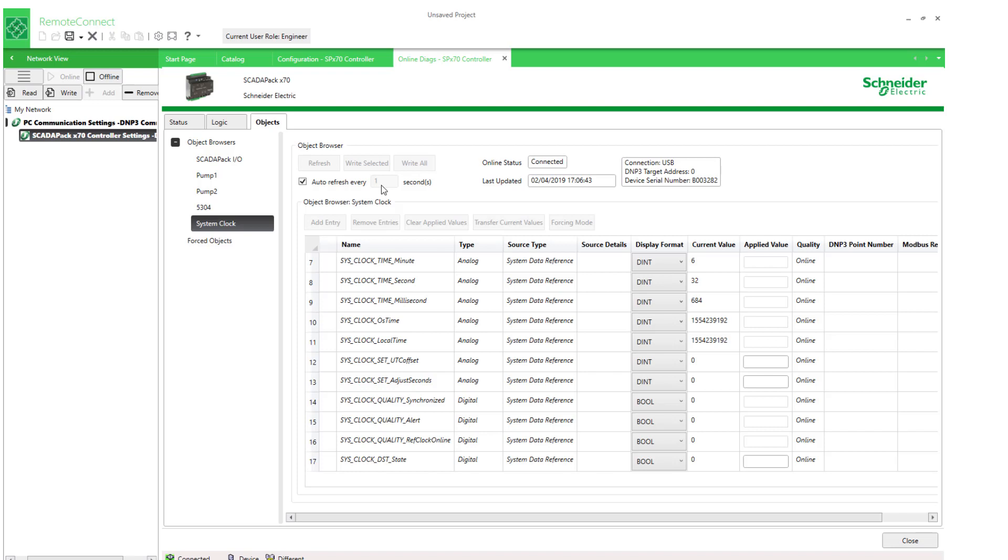Now, when there are many objects in an object browser, a one second refresh interval may not be long enough to complete a file transfer. Recall that a maximum of 15,000 objects are supported. So given the expectation that you will have lots of objects, we have chosen the default refresh interval of five seconds as a more realistic choice.